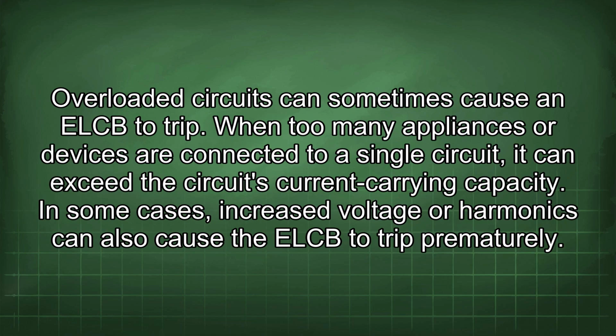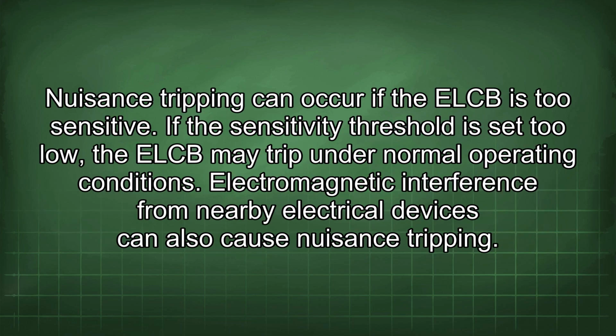Overloaded circuits can sometimes cause an ELCB to trip. When too many appliances or devices are connected to a single circuit, it can exceed the circuit's current carrying capacity. In some cases, increased voltage or harmonics can also cause the ELCB to trip prematurely. Nuisance tripping can occur if the ELCB is too sensitive. If the sensitivity threshold is set too low, the ELCB may trip under normal operating conditions. The electromagnetic interference from nearby electrical devices can also cause nuisance tripping.